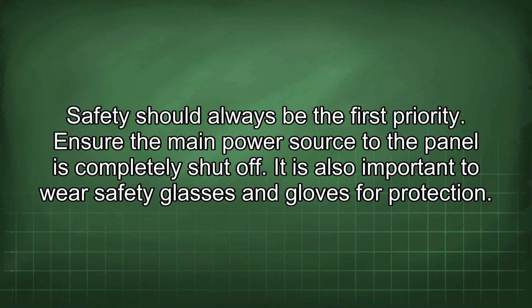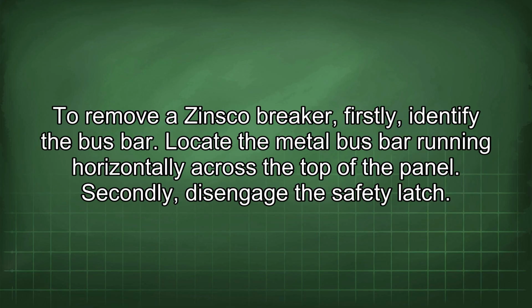Safety should always be the first priority. Ensure the main power source to the panel is completely shut off. It is also important to wear safety glasses and gloves for protection. To remove a Zinsco breaker, firstly identify the bus bar. Locate the metal bus bar running horizontally across the top of the panel.